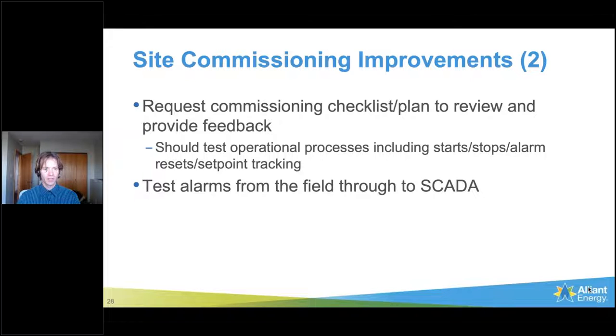Some additional site commissioning improvements. As mentioned earlier by Dan, there really should be more operational processes identified at the start that you want to check out as part of commissioning. Instead of it just being a capacity test and communication check for the system, there should be the ability to test starting the system from offline, stopping the system to that offline state, alarm resets, and set point tracking—all spelled out specifically in the commissioning process, specifying more to the integrator rather than relying on them to put together their own package covering all your needs.